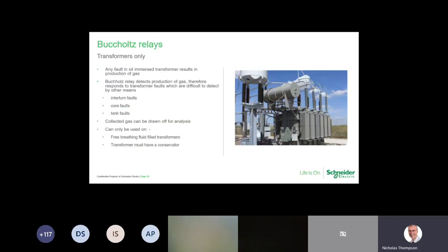Now, moving on to some other forms of protection we've got for transformers, particularly on the larger transformers, which are oil immersed or fluid filled transformers. They're referred to as a Buchholz relay. It's not a protection relay in its own right. It's got contacts in there which will close, and then will close the circuit to the protection relay in the circuit breaker. So they do need to be hardwired to the circuit breaker which is feeding the protection relay.